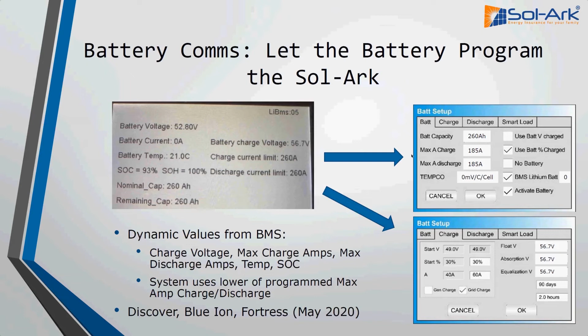Here we go with some more settings. The discharge tab. So your shutdown voltage or percentage, this is just when the inverter stops putting out AC power to protect the battery. Low battery doesn't really do a whole lot. It just makes the battery icon on the home screen turn yellow to give the user a warning that, hey, your battery's getting kind of low. And then restart is whenever we'll resume AC output. So if you were to drain the battery all the way to 20%, the inverter would shut down, recharge off the solar panels until it hit 50%, and then it would resume powering loads on the AC side.